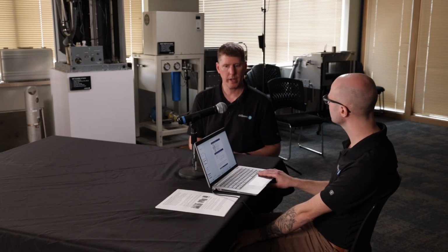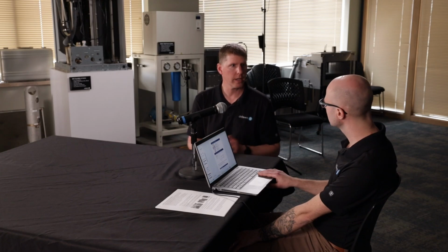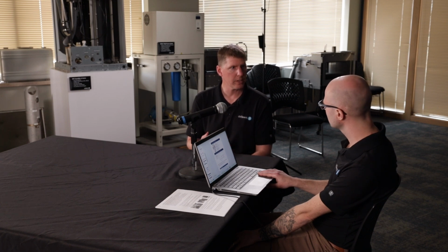The air temperature has a big part of it. Mm-hmm. When you're designing it, plan for your worst case. If the air is warmer, it's going to dissipate faster, and so understanding that is a key piece. If airflow volume changes, now you've changed your mass, so you maybe need more or less moisture addition. So making sure that you're solid when we talk about load and also your dispersion. What is the air volume? What is the air temperature? And how is it going to go through, to make sure I'm balancing that from a performance standpoint?